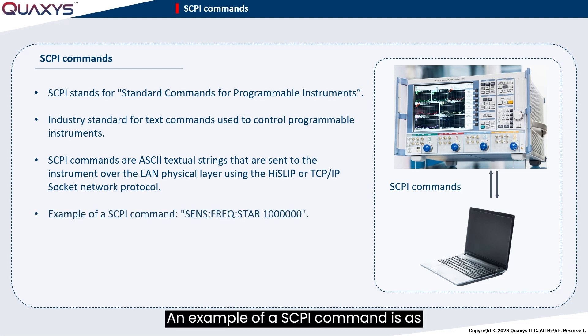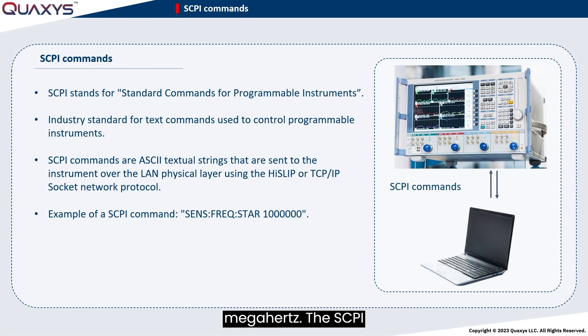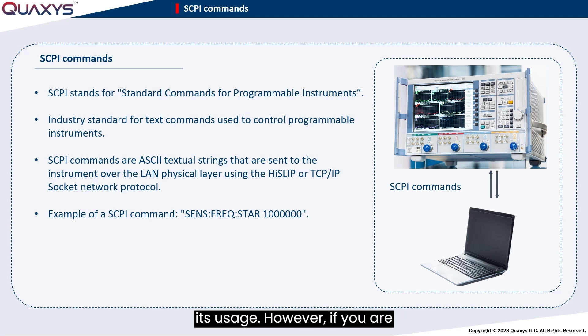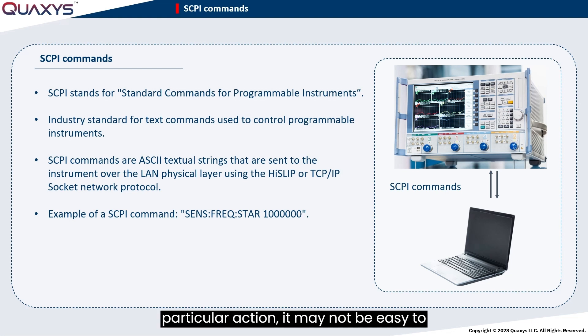An example of a SCPI command is as follows. This command instructs the VNA to set the start frequency of the measurement to 1 MHz. The SCPI command typically provides context for its usage. However, if you are unfamiliar with the command for a particular action, it may not be easy to generate it accurately. This is where the programming manual becomes especially valuable, as it contains the necessary SCPI commands to help you build your code.